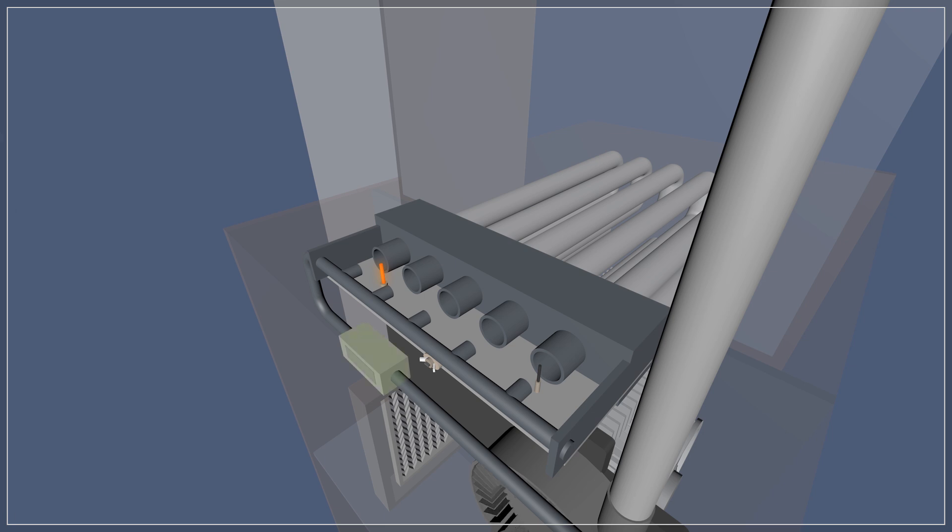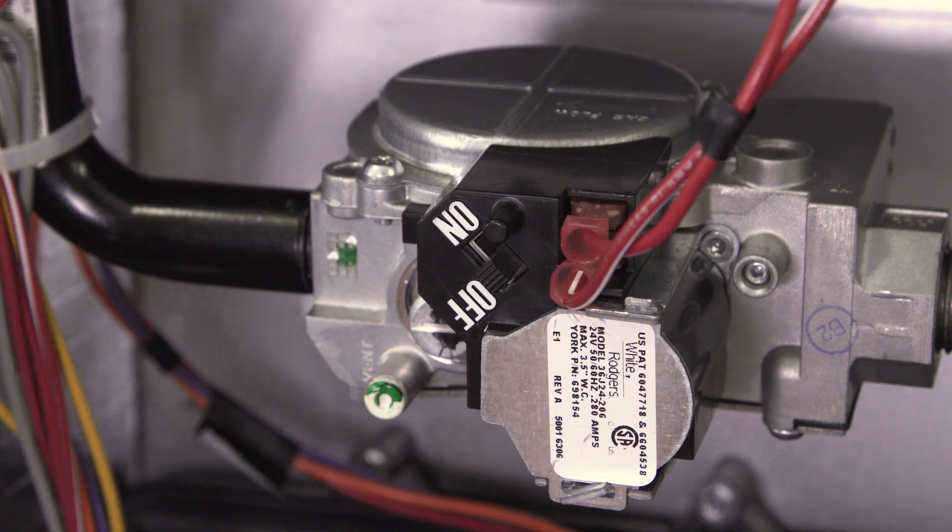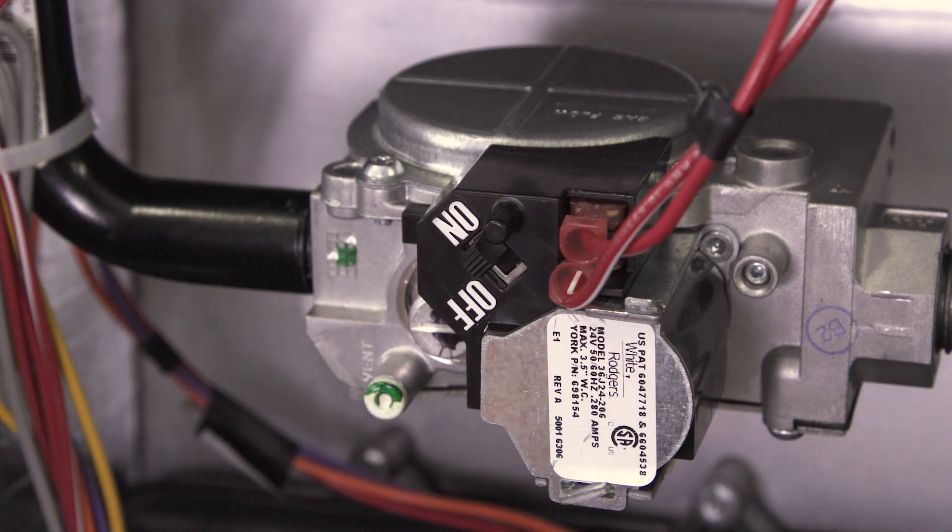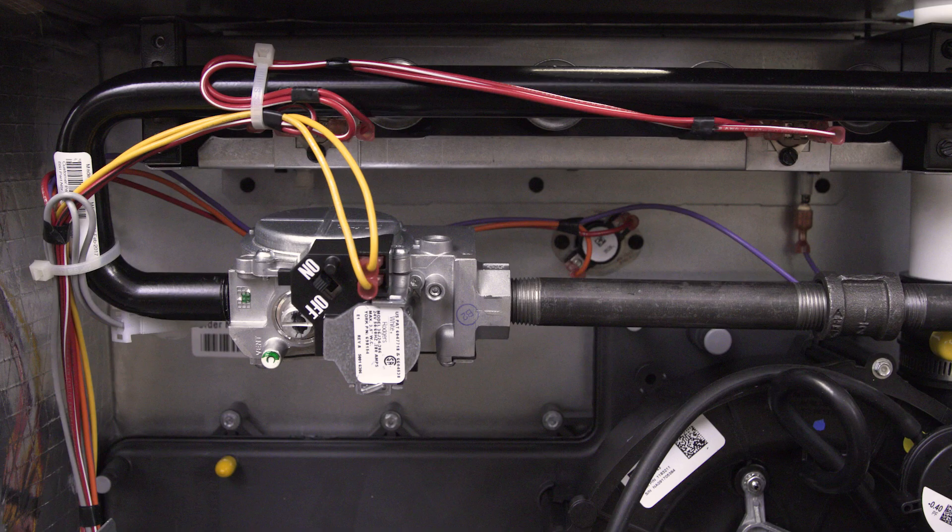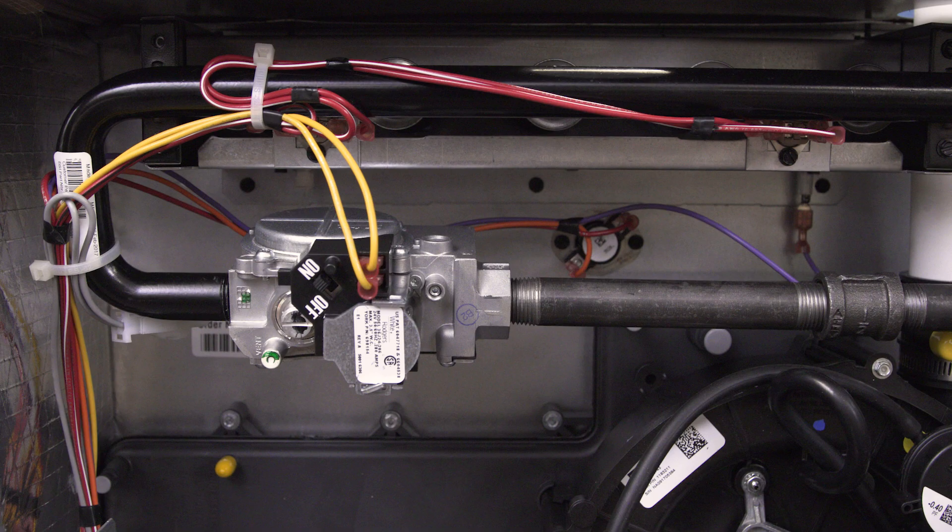As the igniter glows, the gas valve will open and the burners will ignite. If there's no flame present, then check to see if the gas valve is on. If there's still no flame, then call a professional, as the gas valve solenoid could be faulty or there could be low gas pressure.